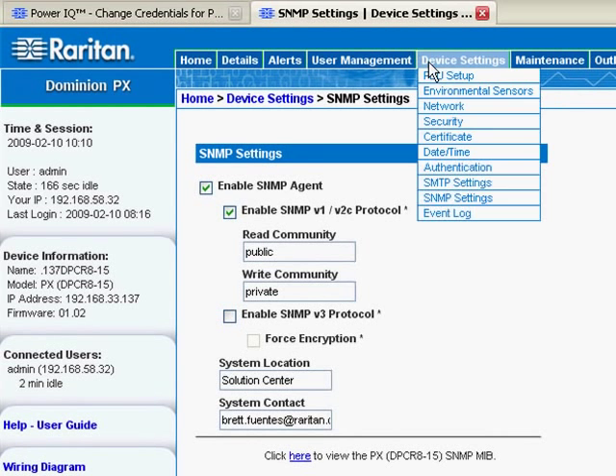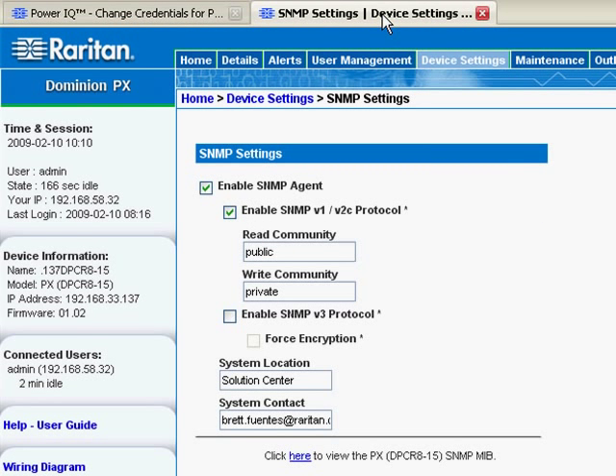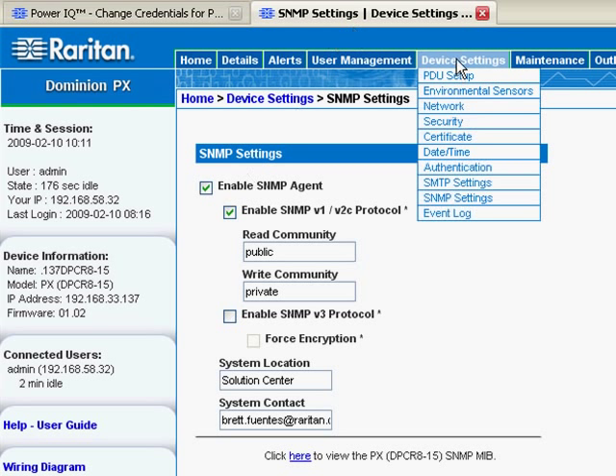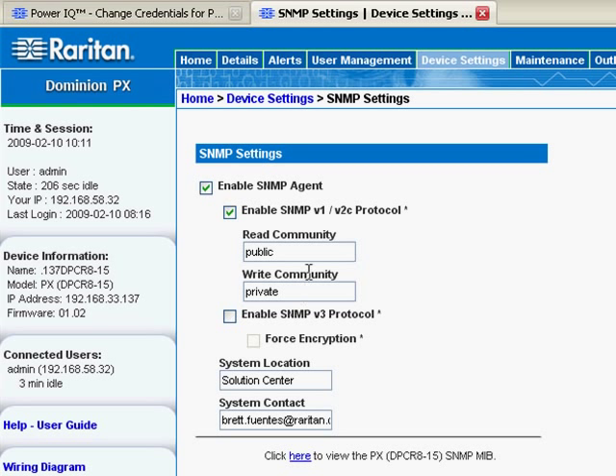Power data starts at the rack PDU. In this particular case, I'm starting on my Dominion PX GUI, and you need to make sure that the rack PDU has, from its device settings, under SNMP settings, has SNMP enabled, enable SNMP v1 v2 protocol, and record the write community string, W-R-I-T-E, because you're going to have to enter this write community string, in this case it's private, onto PowerIQ, so PowerIQ can pull the energy data via SNMP.